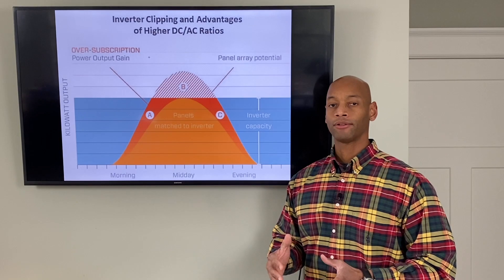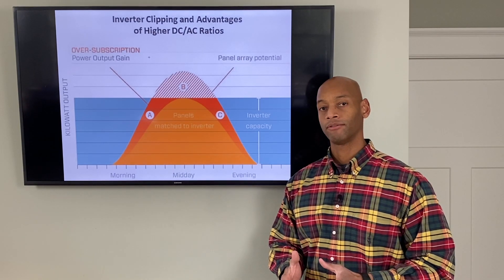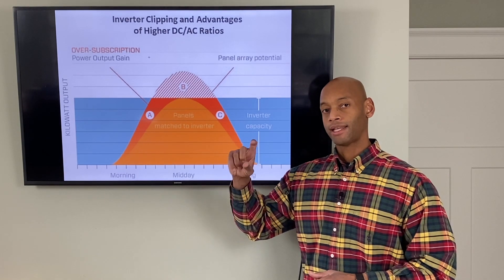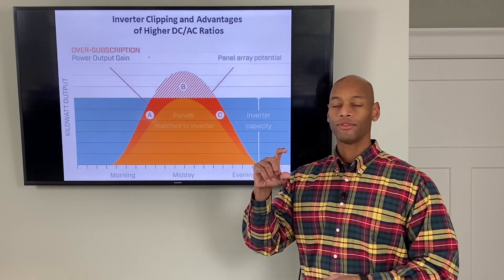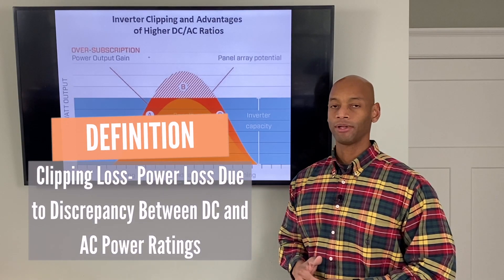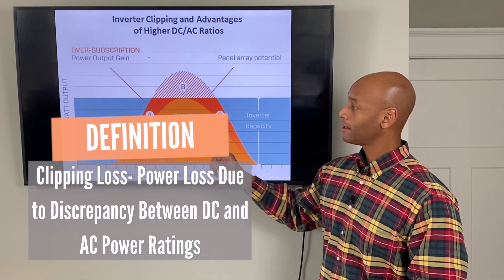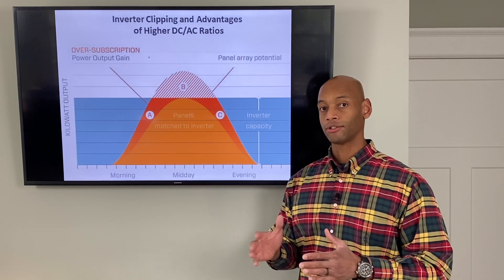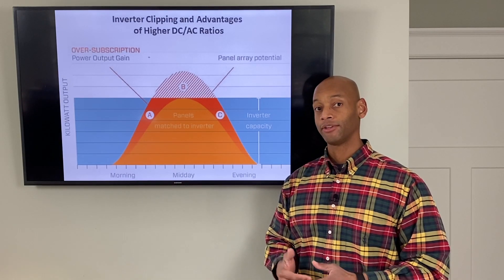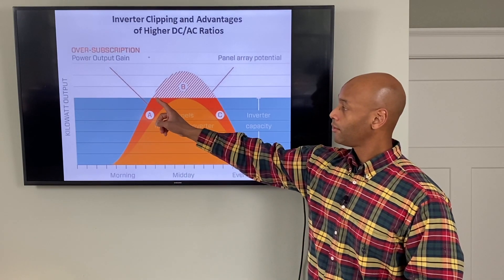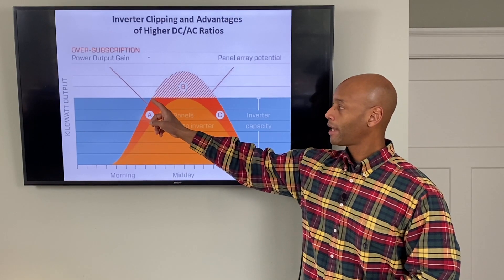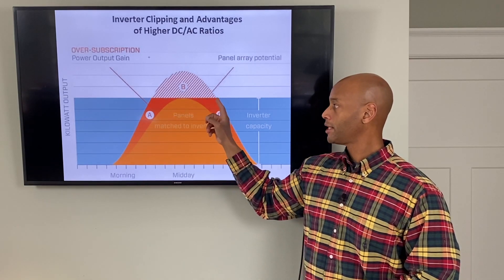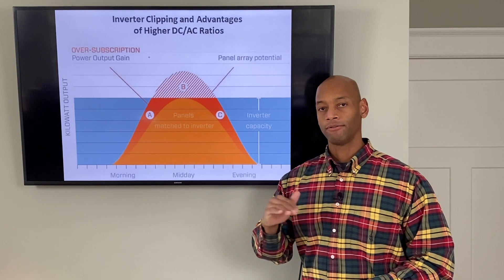If you hook those solar panels to an inverter or group of micro inverters with an AC power rating of only six kilowatts, then that difference — that 1.5 kilowatt difference — is called the clipping loss or clipping factor. What it's showing is that under very high sunlight and cool temperatures, where solar panels can operate at maximum efficiency, the solar panels have the potential to produce more power, but the power output is being limited by the inverter's power rating.